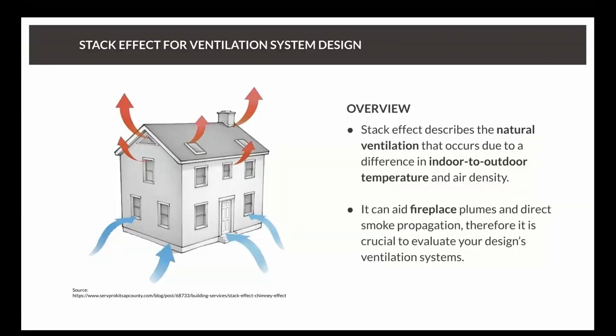So, talking about the stack effect for today. The stack effect works when we have a difference in temperature — primarily — or height as well. You can see here there's a building where cool air enters at the lower levels, heats up inside through various reasons such as heating or just from occupants, and then the hot air rises and leaves at the top. We're focusing primarily around the chimney and how that affects airflow internally — whether you're looking at winter with a fireplace inside, or summer with active cooling to bring the temperature down.